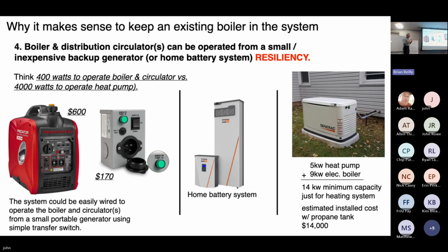So if I'm going to use a heat pump and I want to have a full backup, I'm looking at something like this, a Generac or a Kohler generator, maybe 18 or 20 kW. You can do it, but it's a lot more expensive. And certainly if you're putting in substantial amounts of electric resistance heat. And by the way, some of the air and water heat pump systems today come with up to 9 kW of electric resistance heating built right into the unit. The Enertech unit, that was one of the hydro splits that I showed you, actually has 3 stages, 3 kW each, and it will stage them on as necessary.